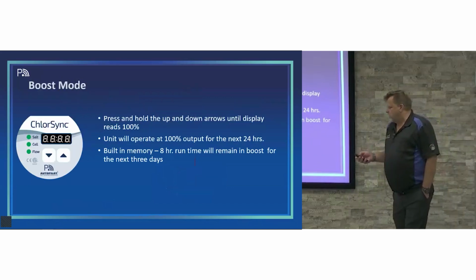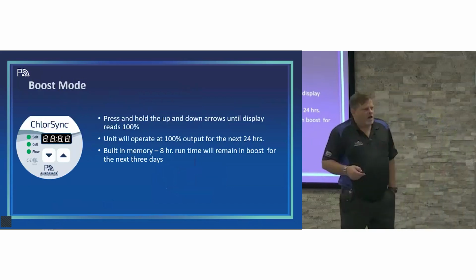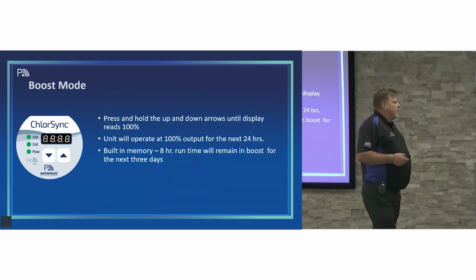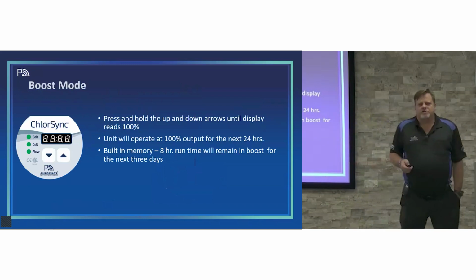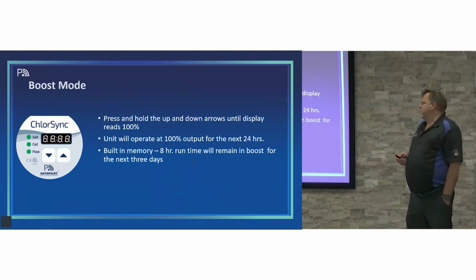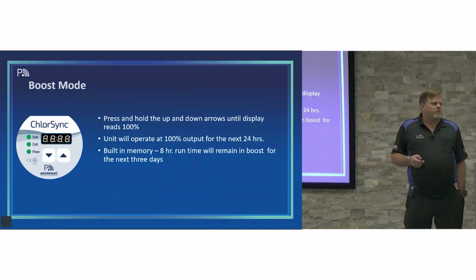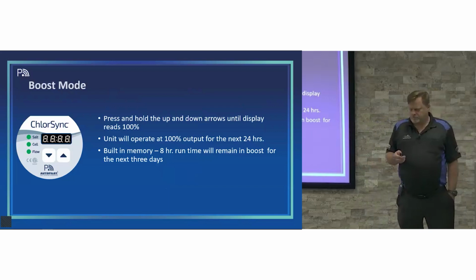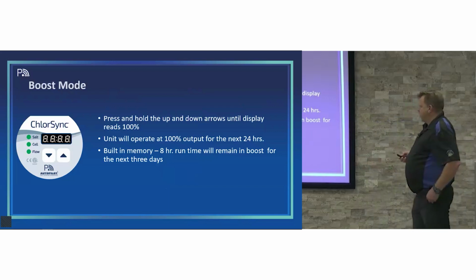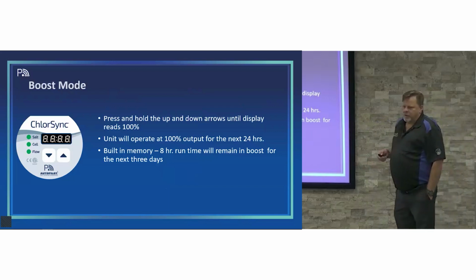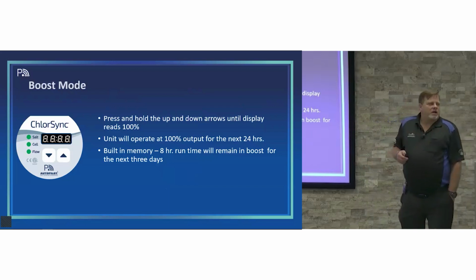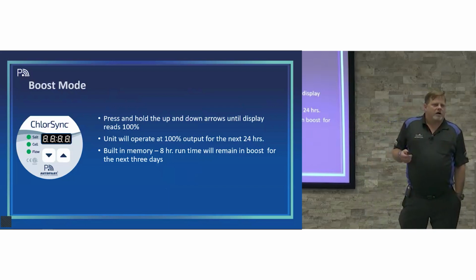So boost cycle: if you don't have the app and you want to put the system in a boost cycle, you simply press the up and down arrows and hold them down for a few seconds, and it will literally read BST, which stands for boost, and 24. And then you can take your fingers off of the up and down arrows. Like we were talking about earlier, if you have an 8-hour pump run time and you don't override the time clock, then it's an 8-hour schedule. It's going to run for 3 days in boost.